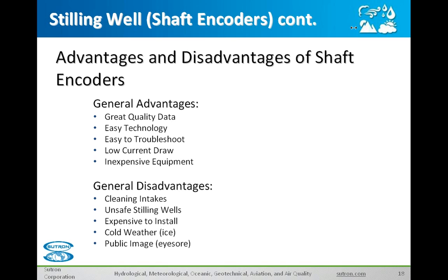Some disadvantages of using a shaft encoder or stilling well: those intakes not only take in water, but in certain events they may also take in silt and debris, which can make your data a little more erroneous. You do have to maintain that, which can include climbing in and cleaning them out, which can also be unsafe. Installing a stilling well can be pricey and expensive, and sometimes difficult with permits depending on where you live. Regarding icy situations, the problem is your float can rest on top of the ice, and as water moves underneath the ice surface, you're not going to really measure the change there.